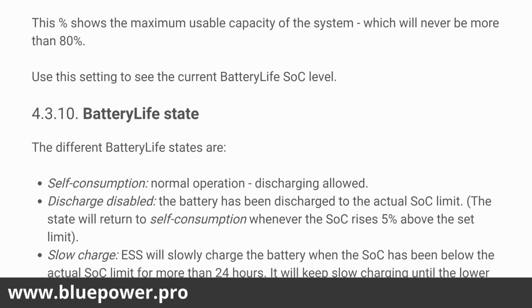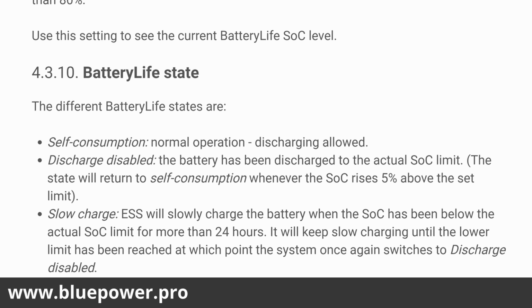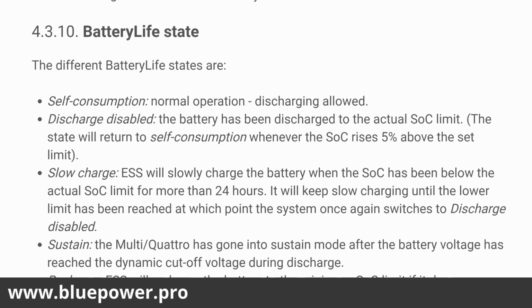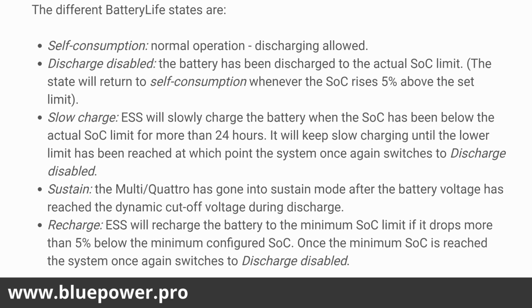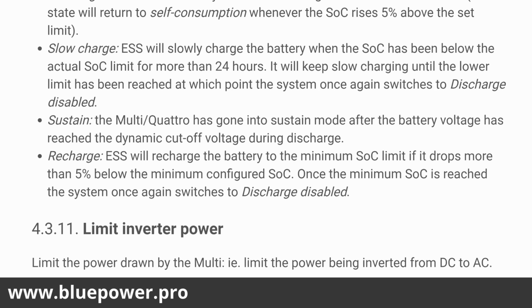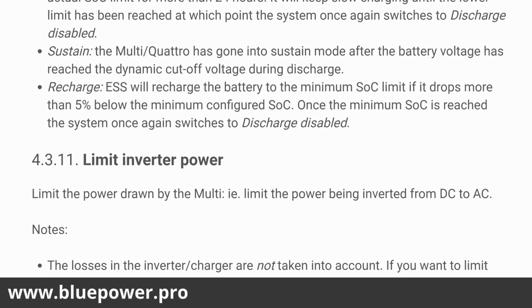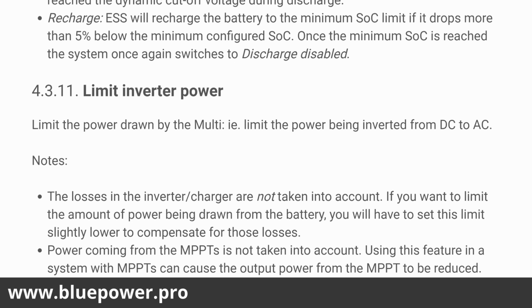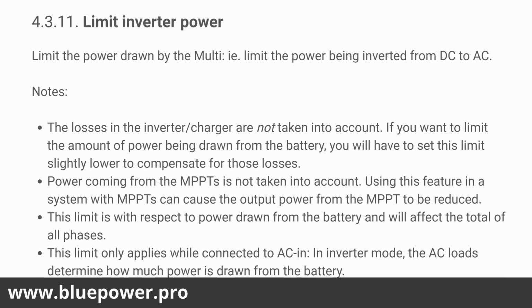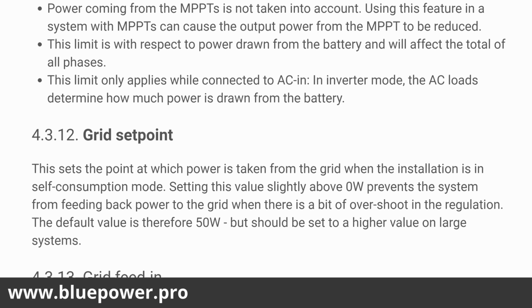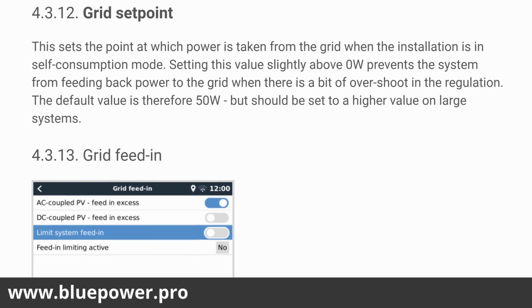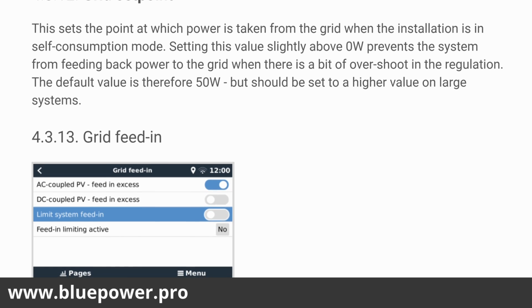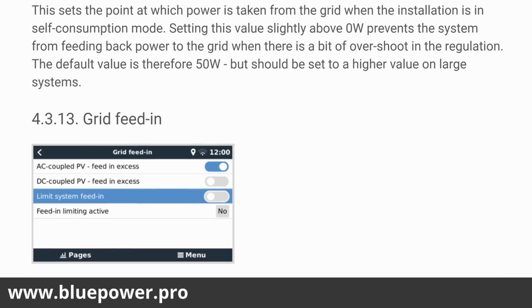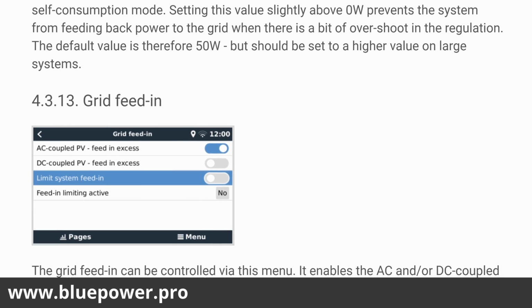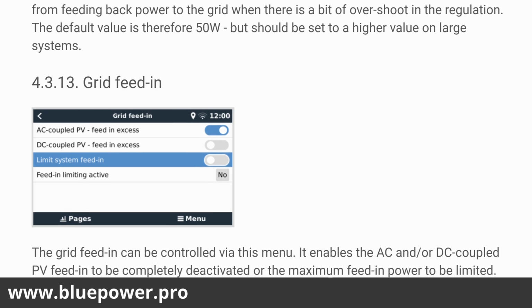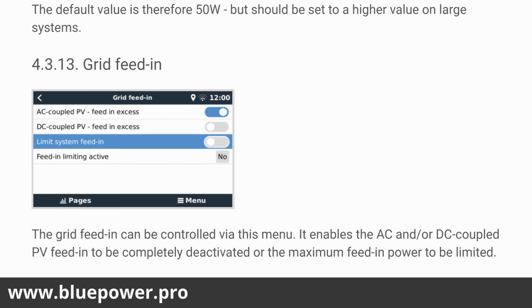So the active limit is going to be the state of charge which the algorithm determines is going to be available to recharge from solar. And battery life states, so that's just the different states that the ESS system is going to be operating in at different state of charge levels and different solar production. Here we can limit the inverter power. That's only applied when you are connected to the grid. Our grid set points, so that's the power that we are going to be drawing from the grid. Most of the times when the system is producing enough PV and the batteries are above the minimum SOC, then you're going to be drawing the grid set point from the grid at all given times.